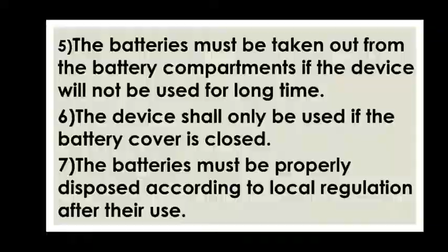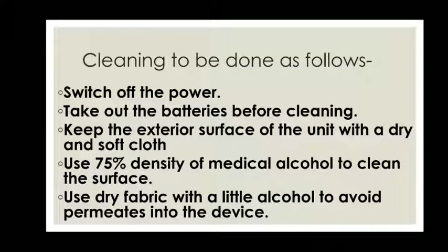How to clean the device? This one has to be known. Cleaning to be done as follows. Switch off the power. Take out the batteries before cleaning. Clean the exterior surface of the unit with a dry and soft cloth. Use 75% density medical alcohol to clean the surface. Use a dry fabric, meaning you can use a cloth with a little alcohol to avoid it permeating into the device.